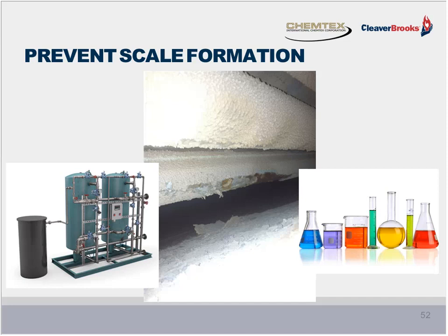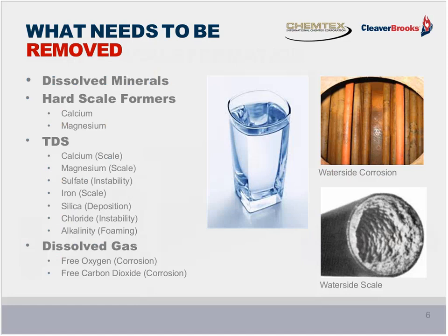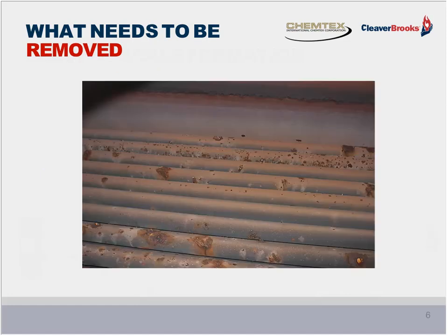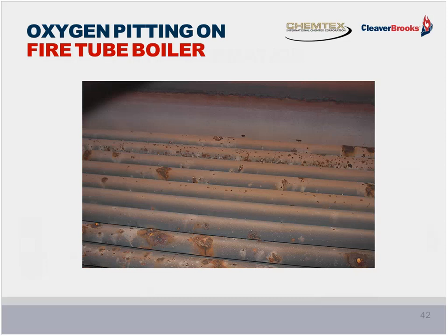A sound water treatment program will use both to affect the best possible outcome for the boiler and for the connected system. And lastly, we need to concern ourselves with the dissolved gases, with the main culprit being dissolved oxygen, which can eat away at boiler tubes very quickly and aggressively, forming blisters on the tubes under which you will find pinhole perforations right through the tube.